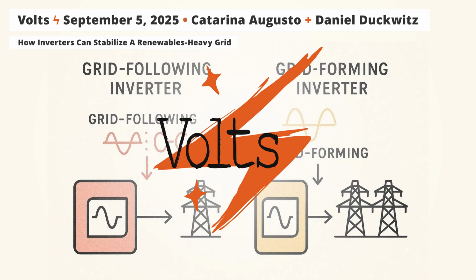When connecting an inverter, the control system needs to make sure the current of the inverter is synchronous to the grid voltage, so it has the right synchronous AC waveform to feed power to the grid. To do that, grid following inverters observe the voltage, calculate the frequency based on the observed voltage, and then follow the grid with their current. They're basically observing what is happening out there and synchronizing according to what they observed - matching the grid's conditions so they can feed power.